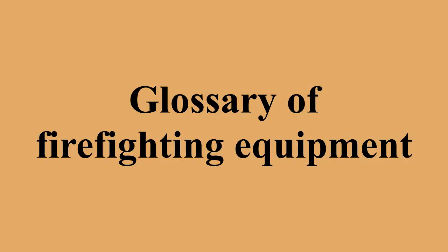Appliance, term for fire suppression equipment used by firefighters to manage or direct a water stream. APW, air pressurized water fire extinguisher, partially filled with water and then pressurized with an air pump, popular in the US in the 2.5 gallon size, rated 2A. Aqueous film forming foam, bubbles that act as surfactant to coat and penetrate ordinary fuels to prevent them from burning at normal temperatures, also used on Class B fires to spread a non-volatile film over the surface of the fuel, applied using eductor, a compressed air foam system, and pumped through fire hose to a foam nozzle.